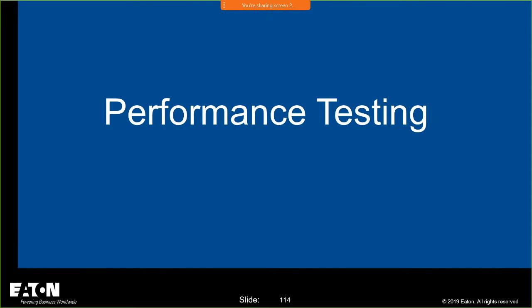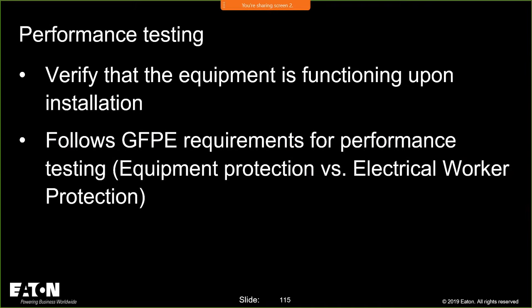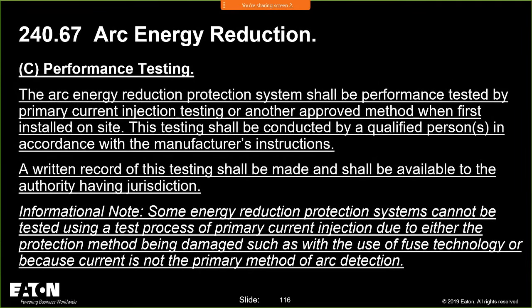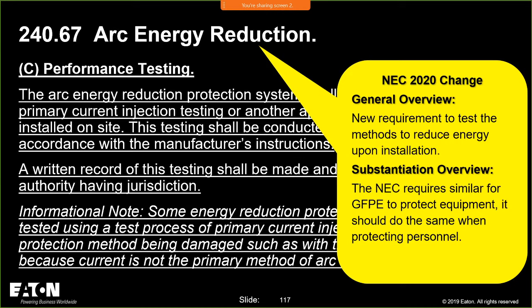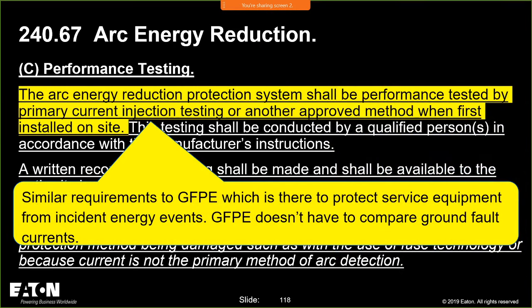Now, performance testing. There's a new requirement that says you have to verify that this equipment is functioning on installation. I don't recommend that you test that the fuse works. Okay, I don't recommend that you inject current through the fuse to watch it open. I mean, my Bussmann sales guys would love that, but you don't want to do that. But you do have to do, just like we do with ground fault protection of equipment, in 240.67 just like in 230.95, the requirement that you performance test by primary current injection test or an approved equivalent means or another approved method when first installed on site. It's similar to GFPE.